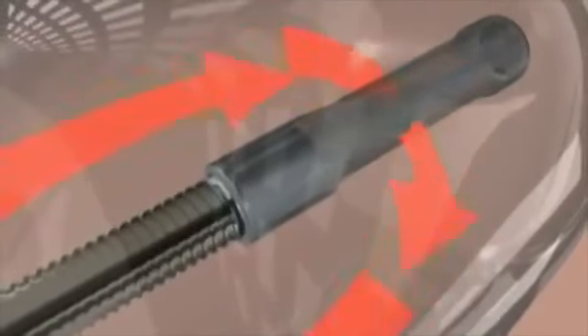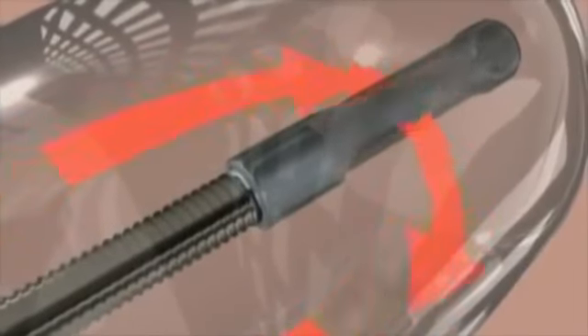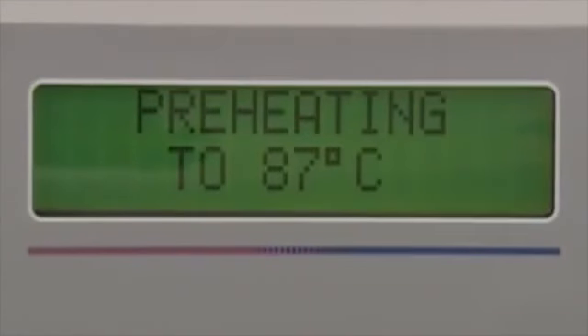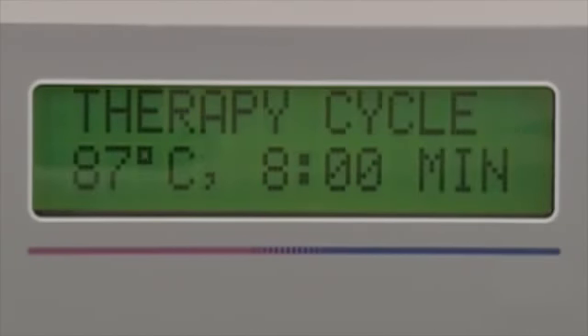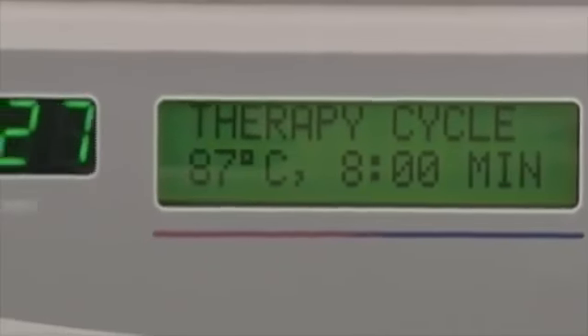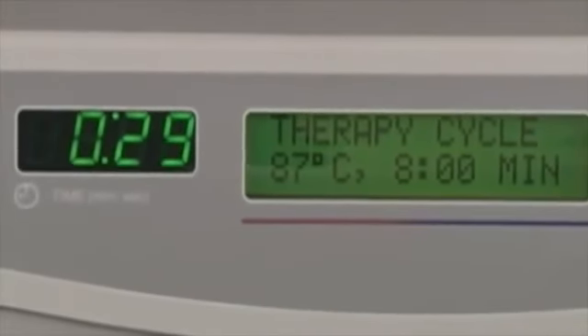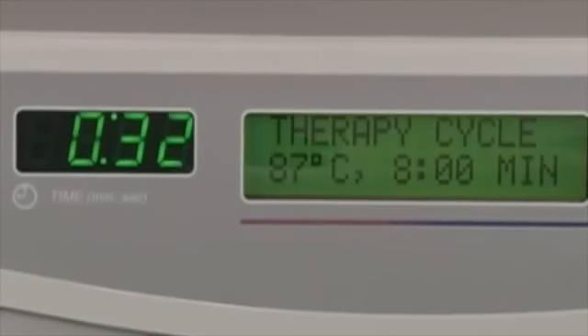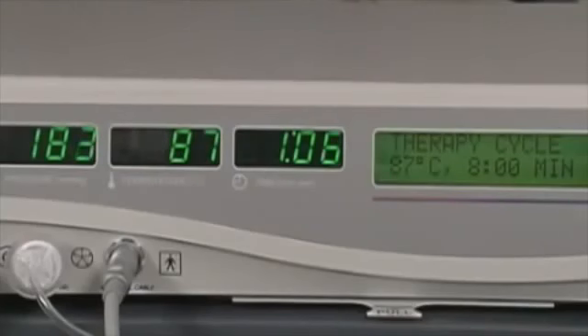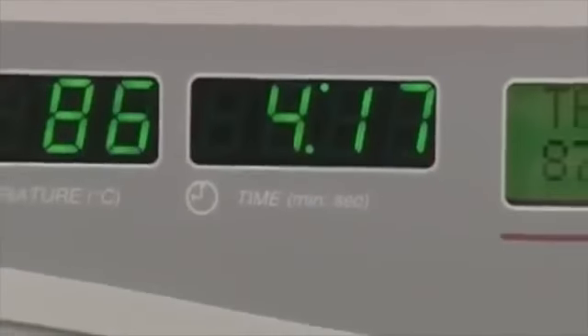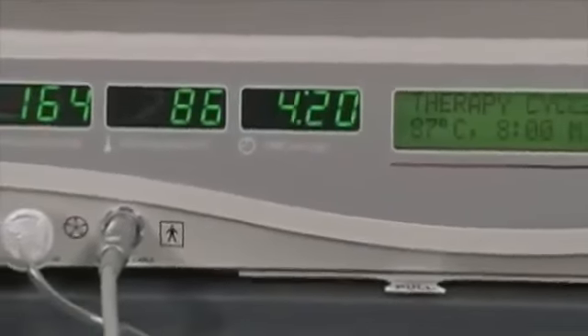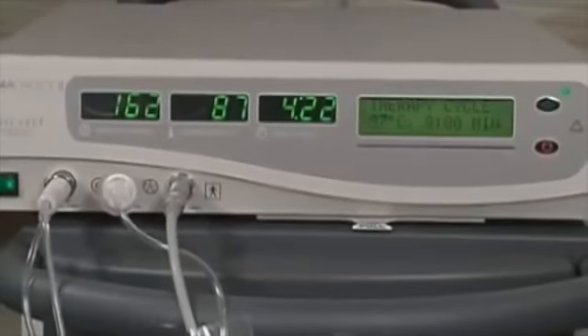The impeller at the tip of the catheter begins to circulate the heated fluid inside the balloon and continues throughout the therapy cycle. Once 87 degrees is reached, an audible tone indicates the automatic activation of the 8-minute therapy cycle. Therapy time elapsed is shown on the controller's time display. After the preheat cycle is complete, the time resets to 0 minutes and seconds. The displayed time is the exact therapy time. Throughout the procedure, the controller will continuously monitor pressure, regulate temperature, and track therapy time.